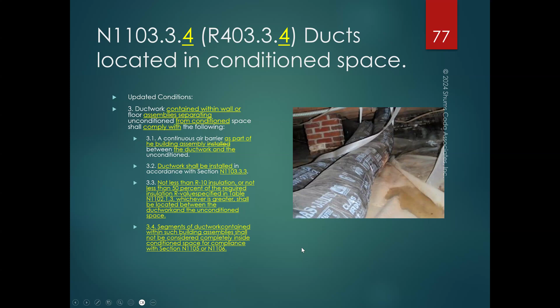So if we've got a basement and a first floor, and we're putting all the ductwork in between those 2 floors, that's within the thermal envelope, that's within the conditioned space, and so we wouldn't need to comply with this information. Obviously, we'd have to seal it up, but we don't have to put duct insulation around it. Now that R10 is a change. It used to be an R8, so we've gone up another 2.